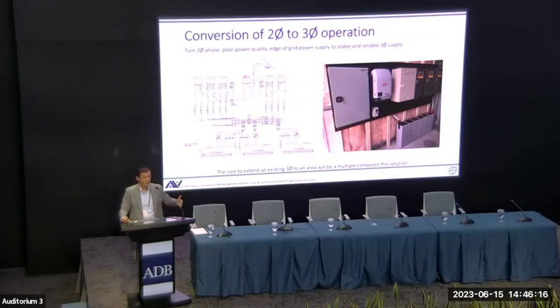So what do you do there? A lot of diesel gensets are typically required, but in this case we can cut that out. We can use the single-phase line and convert it behind the meter. Then, adding solar on top of that, we can provide around 90% of the power requirements, with the single-phase or 2-phase line just trickling in to charge the battery.